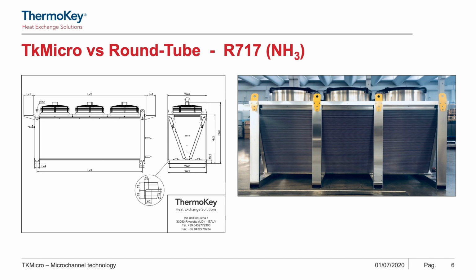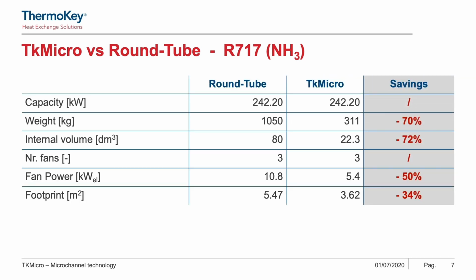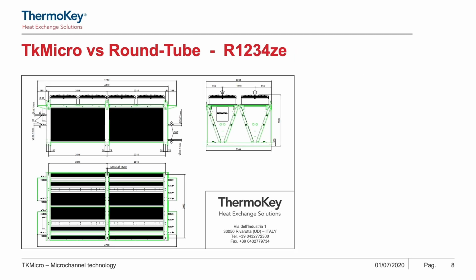Said this, if we compare a remote condenser under the same capacity conditions, we immediately can recognize that we can benefit by a significant reduction of weight up to 70%, a reduction of internal volume up to 72%, and moreover also a reduction of the fan power up to 50%. Finally, the footprint can be reduced further up to 34% thanks to more compact sizes of microchannel cores compared to round tube coils.